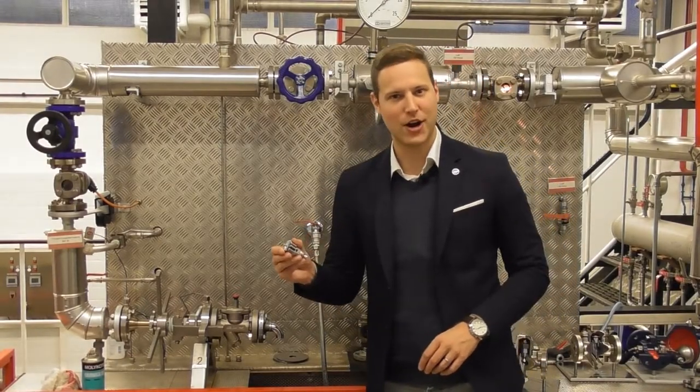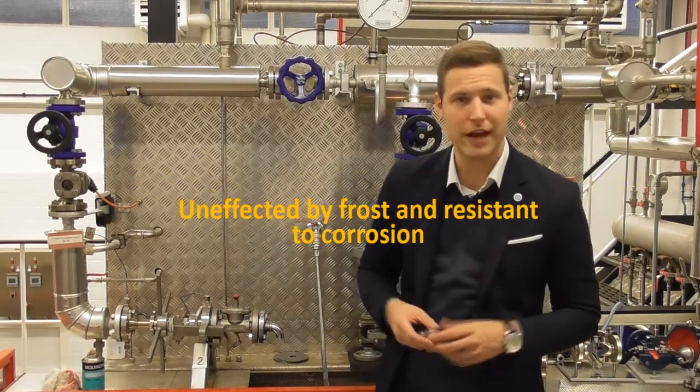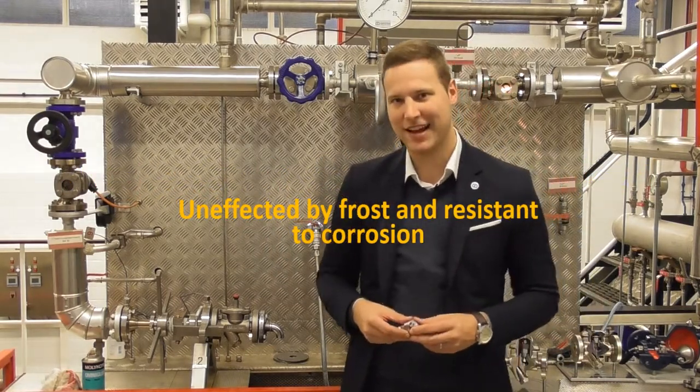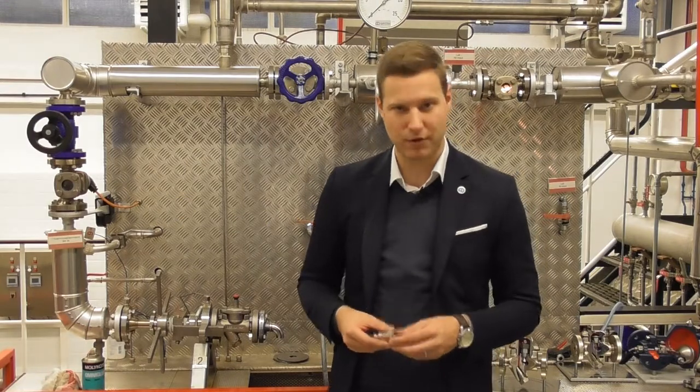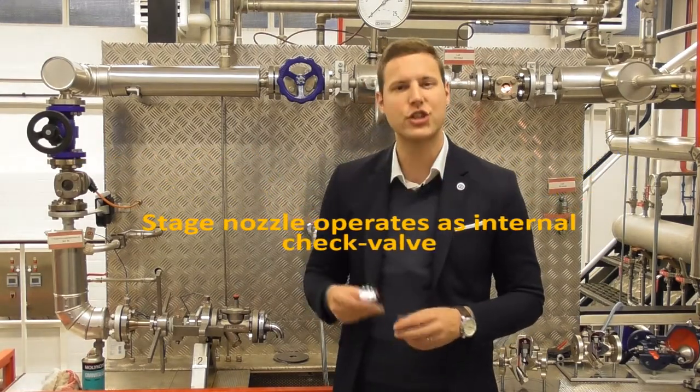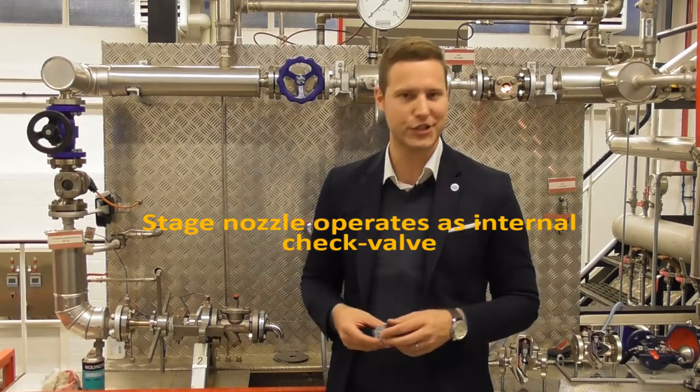These steam traps are unaffected by frost, resistant to corrosion and require little maintenance. Water hammer damages and backflow of condensate are minimized because the stage nozzle will also operate as an internal check valve.